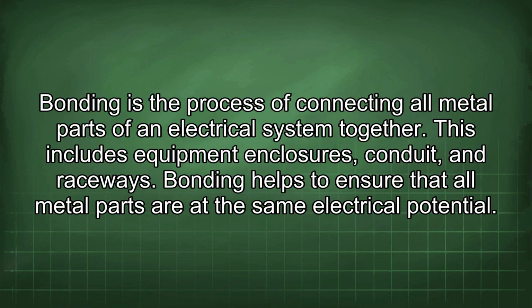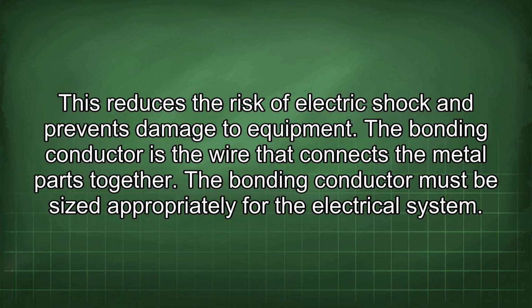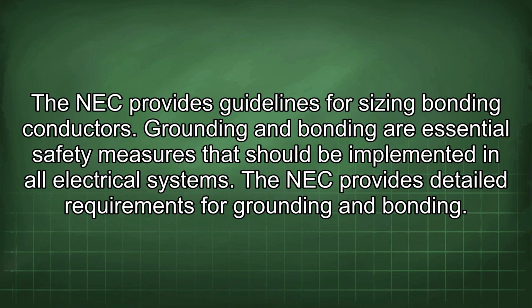Bonding is the process of connecting all metal parts of an electrical system together. This includes equipment enclosures, conduit, and raceways. Bonding helps to ensure that all metal parts are at the same electrical potential. This reduces the risk of electric shock and prevents damage to equipment. The bonding conductor is the wire that connects the metal parts together. The bonding conductor must be sized appropriately for the electrical system. The NEC provides guidelines for sizing bonding conductors.